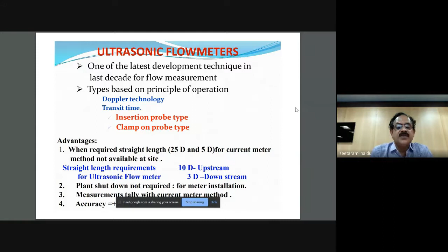Here the typical requirement is 10D upstream length and 3D downstream, and this is the minimum requirement. If you don't have this kind of straight length upstream, we can't use ultrasonic. But there are situations where we have used it in very constrained passages also, for carrying out RMU, as in Bhadgar, Veer, etc., to somehow assess the efficiency in order to have an upgraded turbine in the future.